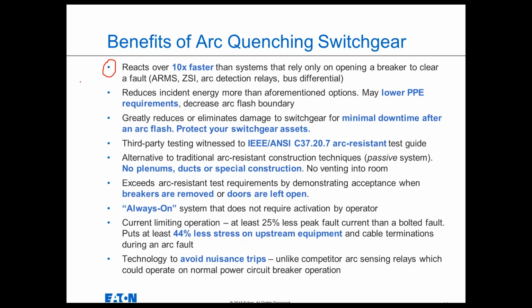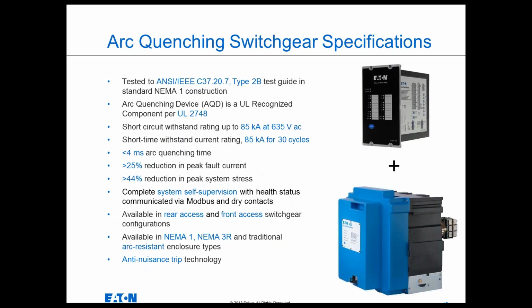But we've developed technology that actually interlocks the operation of all the circuit breakers with the arc detection system so that you eliminate that risk of nuisance operation when you get that high current and light from a feeder breaker clearing a downstream fault. Talk a couple quick specifications and then hit on exactly how the system works.